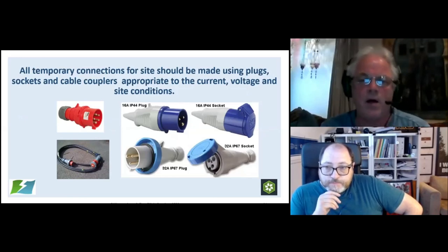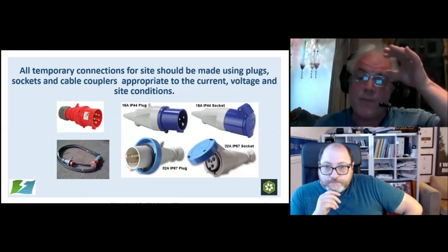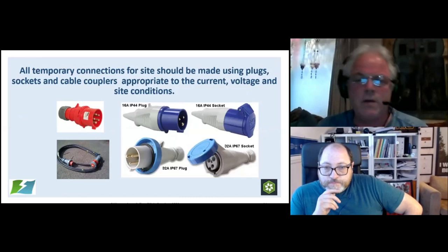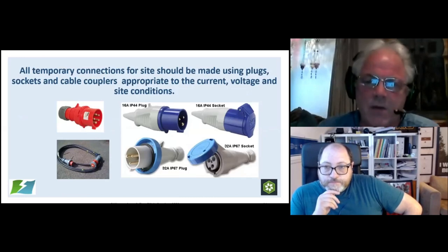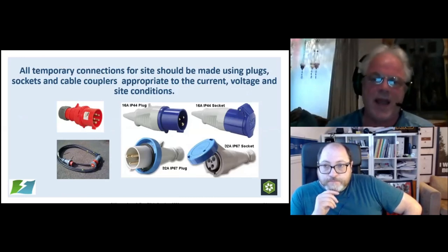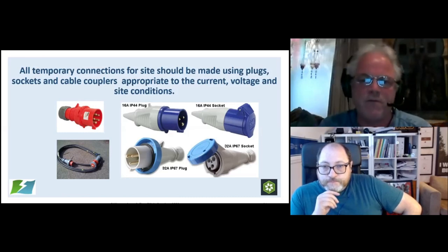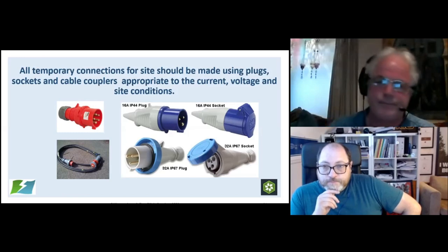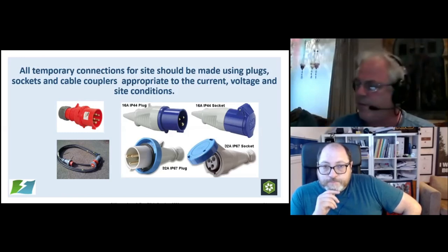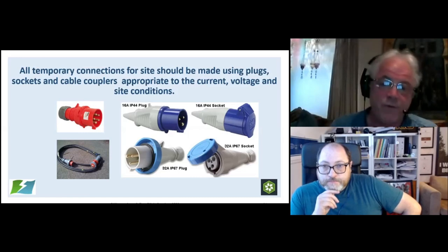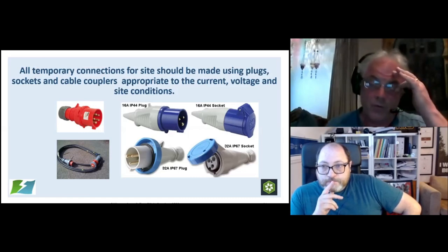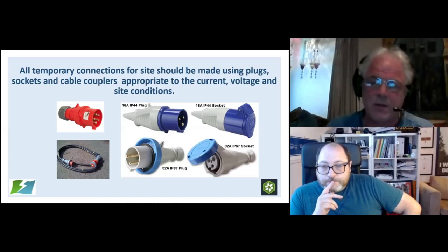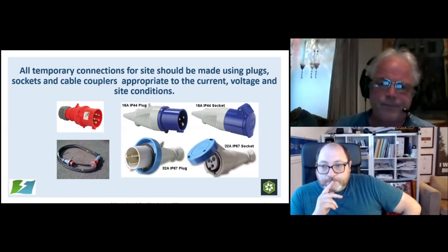Okay, remember they are IP44 normally as a minimum if they are properly made off and properly connected, mated all the way. Also, remember that the size of the cable needs to be correct so that it actually fills the gland at the back. If there's room around the cable at the back, water will encroach in from the rear of the socket and you'll get a big bang. Also remember, these are splash proof, IP44. They're not waterproof, so they can't be sitting in puddles or in ponds or whatever.